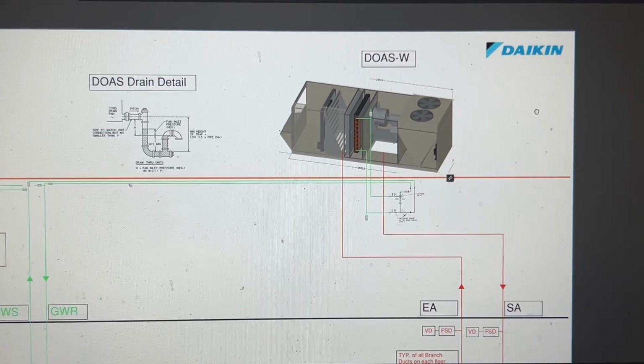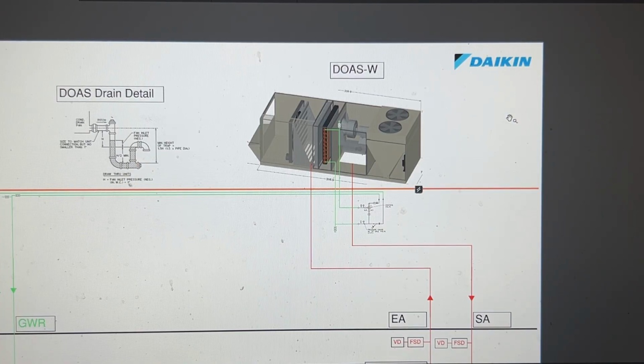But in this particular project, they wanted to be able to have control of the unit. So for that, it will require a lot more controls involvement because they want to be able to adjust set points and adjust fan speed and stuff like that, which requires a lot more work than just being BACnetted out. The only thing that I would say about this is definitely look at the wiring diagram if you have to install one of these, because it will tell you a lot about how the controls portion works.